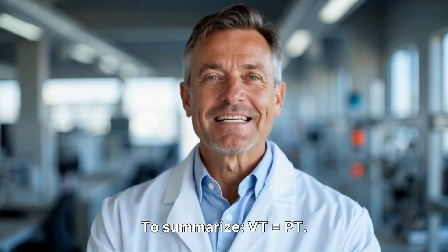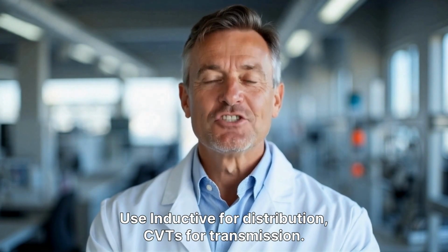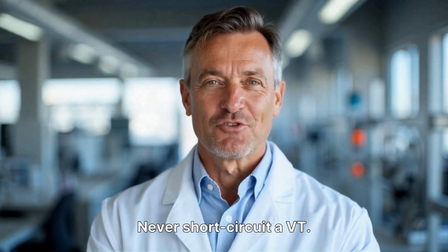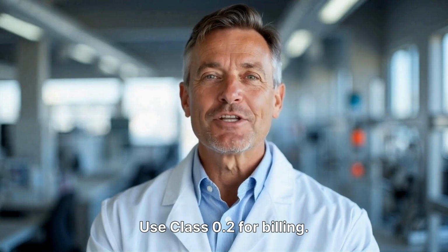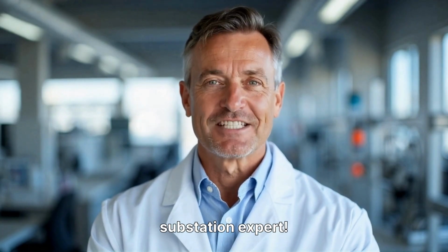To summarize, VT equals PT. Use inductive for distribution, CVTs for transmission. Never short-circuit a VT. Use class 0.2 for billing. I hope this masterclass made you a substation expert.